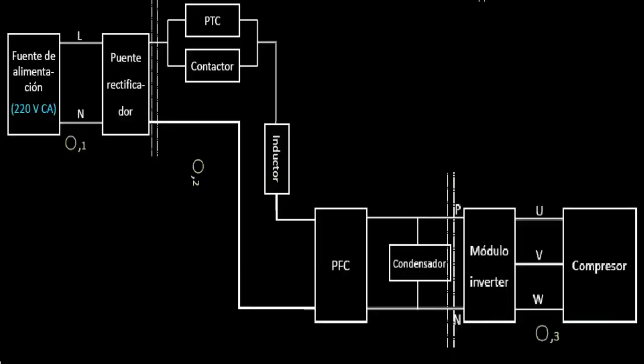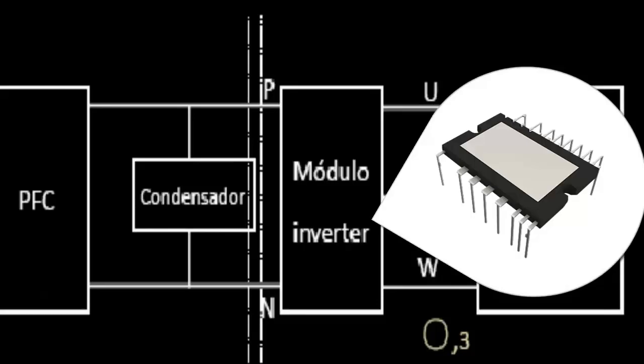Point 8: The inverter module or intelligent power module. The inverter module (IPM) is responsible for controlling and protecting the power supply to the compressor, managing energy efficiently, and controlling the compressor speed. To diagnose the IPM electronic circuit, you can perform the following procedure.